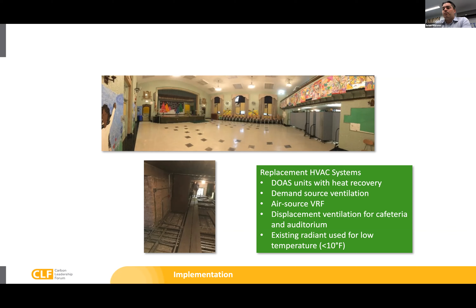So we really wanted to utilize existing infrastructure where it made sense to, and some of the features of the building did allow us to provide creative solutions. Fortunately, this building had a pretty beefy attic. If you can see in the picture on the lower left-hand side, if you're able to duck, you can walk through the attic. This allowed us enough room to distribute DOAS air because we weren't providing the space conditioning to all the various classrooms and offices. That attic was sufficient for the smaller duct size that would be required for dedicated air.